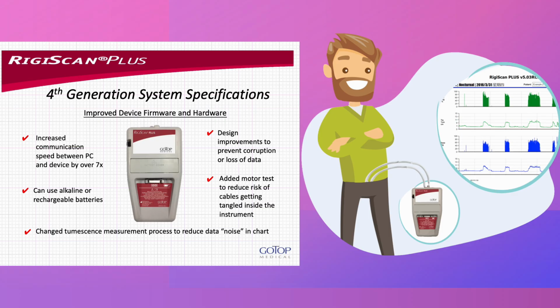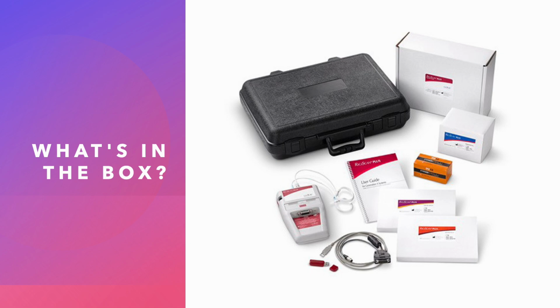RigiScan is now manufactured by GOTOP Medical in the USA and has become the most reliable test for NPT. They have now released the 4th generation system, which has improved firmware and hardware, having increased communication speed between the PC and the device by a factor of 7. It utilizes alkaline or rechargeable batteries and has a changed tumescence measurement process to reduce data noise in the chart, allowing you to get more valuable data. The design has improved to prevent corruption or loss of data and added motor test to reduce risk of cables getting tangled inside the instrument whilst in use.